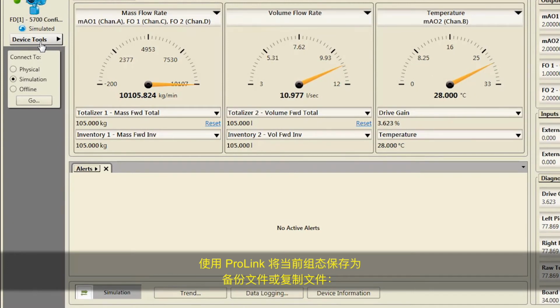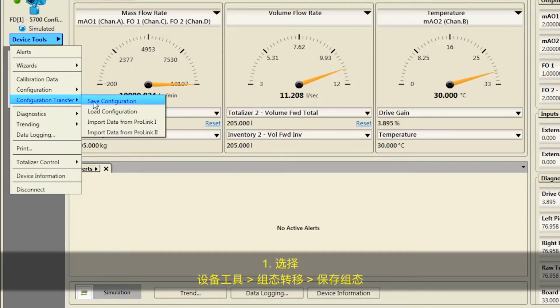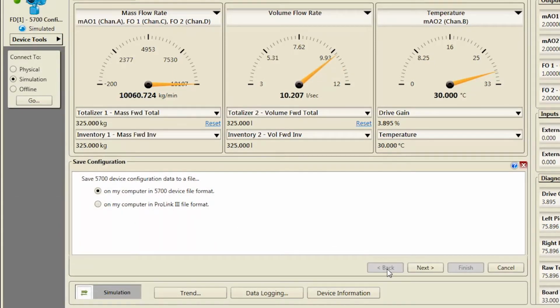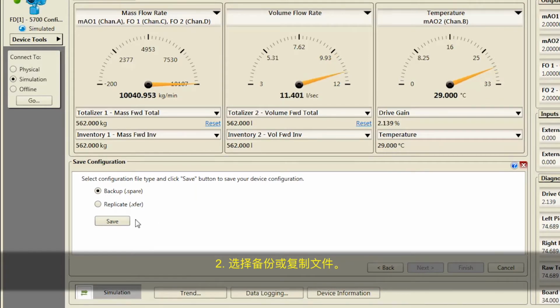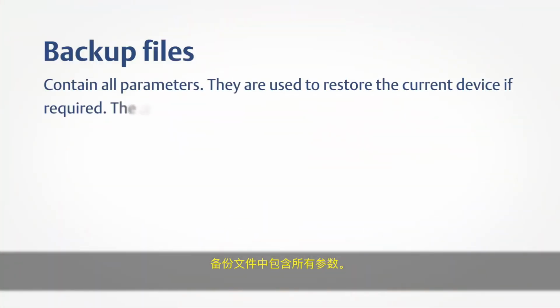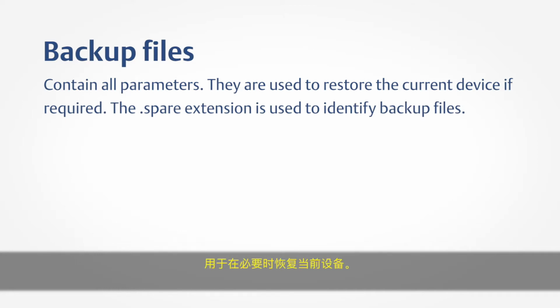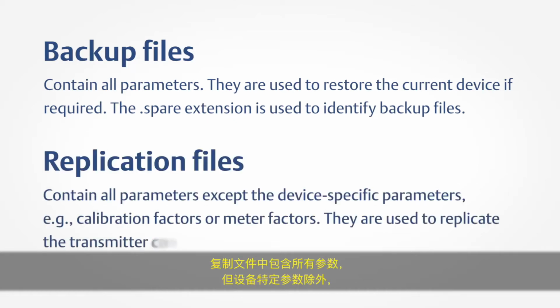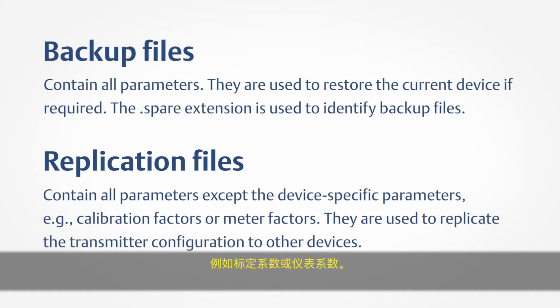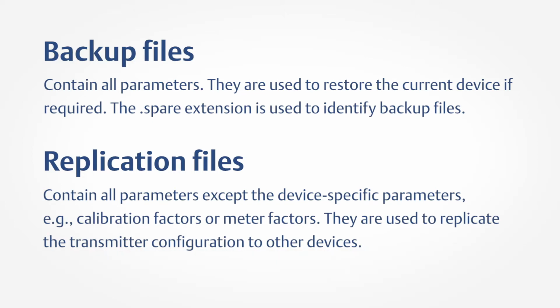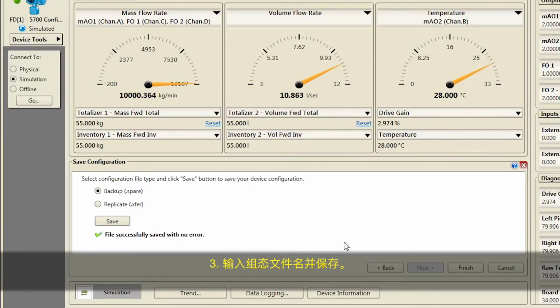To save the current configuration as either a backup file or a replication file using ProLink, first select Device Tools, Configuration Transfer, Save Configuration. Second, choose Backup or Replicate File. Backup files contain all parameters. They are used to restore the current device if required. The spare extension is used to identify backup files. Replication files contain all parameters except the device-specific parameters, for example, calibration factors or meter factors. They are used to replicate the transmitter configuration to other devices. Third, enter the name for this configuration file and save.